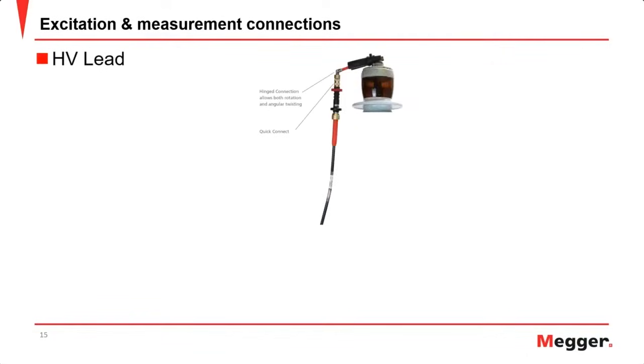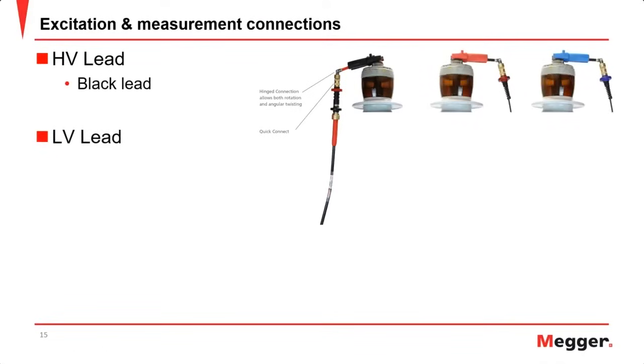Now, when we make the connections to bushings, typically you will have a high voltage lead. This will be where, if you're doing DFR, you're applying 140 volts or 1400 volts RMS, or if you're using a 10 kV power factor test set, this high voltage lead will provide the source for that 10 kV. You will then have two lower voltage leads. This is what you will typically see as a red or a blue lead. And then finally, the ground connection.